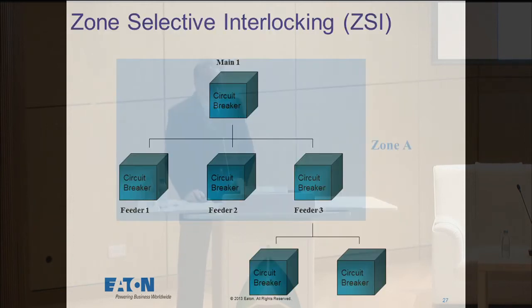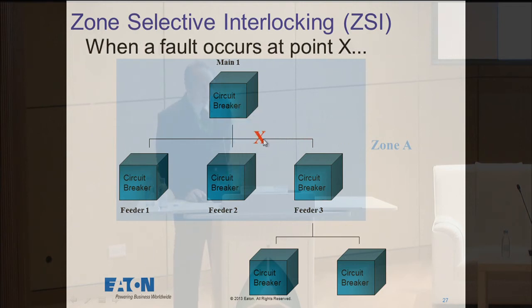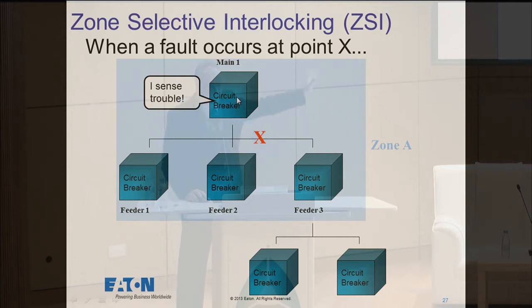We've developed the information to help you with your applications. So here is a cartoon, and it's a very simple thing that we show. One main breaker at the very top, several feeder breakers underneath it. These are in the same zone of protection. They will have a communication set of wires going from breaker to breaker up to the main. In a situation where a fault occurs at this point, this first breaker says, I sense that problem because it's downstream from me. Now, bear with me, the breakers don't actually talk to one another.